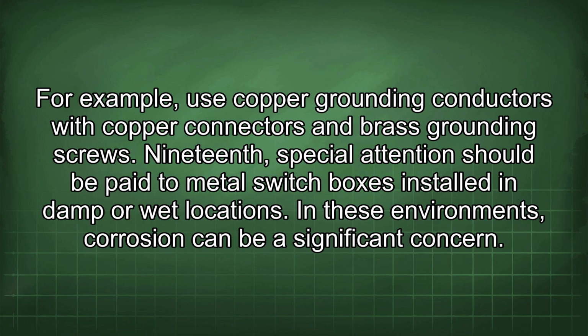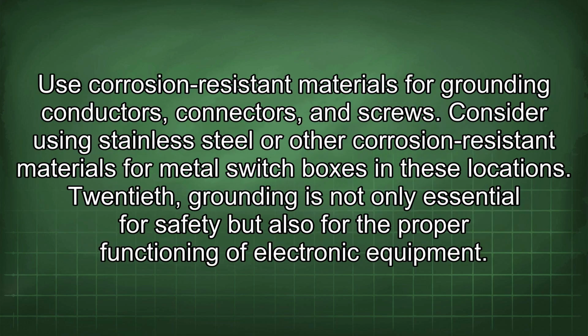19th, special attention should be paid to metal switch boxes installed in damp or wet locations. In these environments, corrosion can be a significant concern. Use corrosion-resistant materials for grounding conductors, connectors, and screws. Consider using stainless steel or other corrosion-resistant materials for metal switch boxes in these locations.